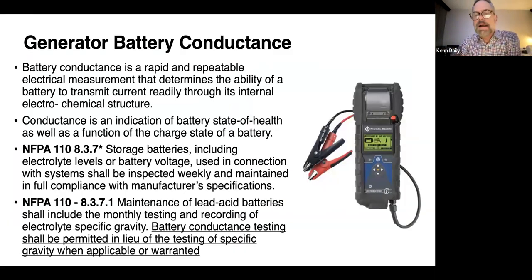Recently, there's been a lot of discussion about the use of maintenance-free batteries, which is absolutely permitted. The code, NFPA 110, says you can use storage batteries that are maintenance-free. But if you use a maintenance-required battery, then you have to do weekly maintenance, and you have to do what's called specific gravity, where you're testing the battery acid once a month with the hydrometer, making sure that the battery has the appropriate levels of battery acid, which is kind of messy and hard to do, et cetera. Well, if you have a maintenance-free battery, you have to get a conductance tester to make sure that the fitness of the battery is appropriate. So it's not just voltage anymore, it is conductance.